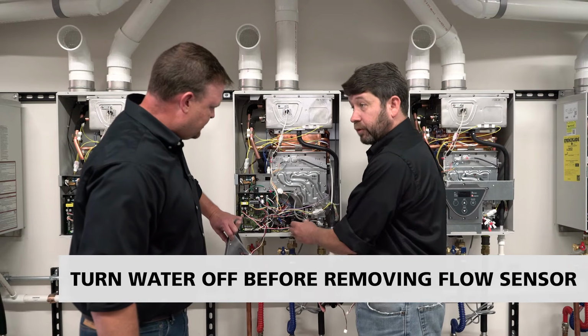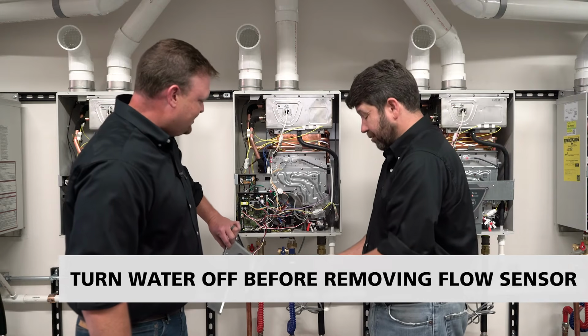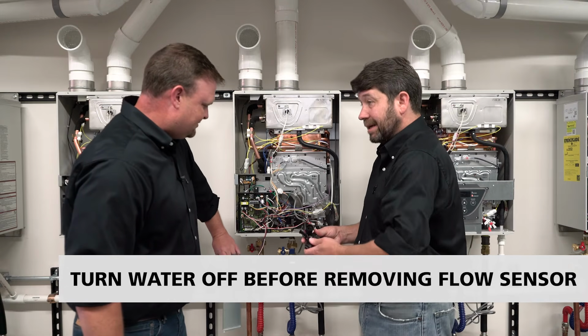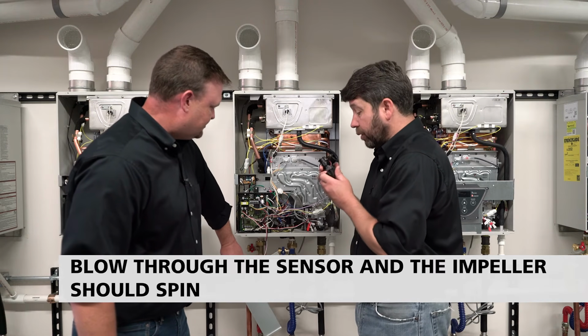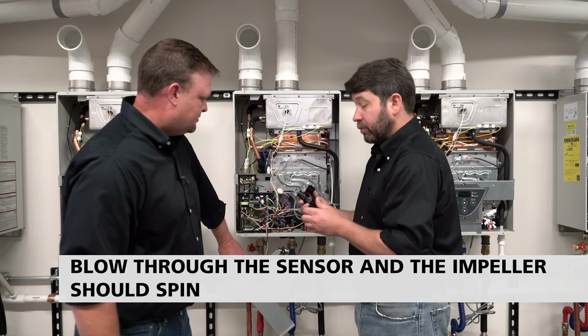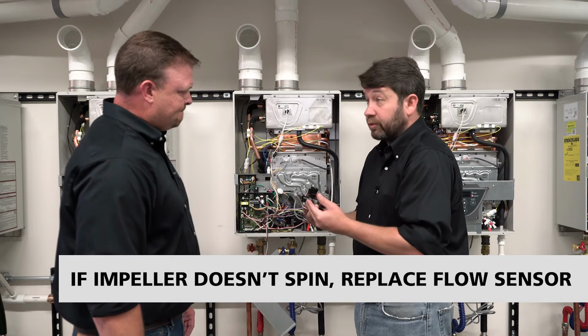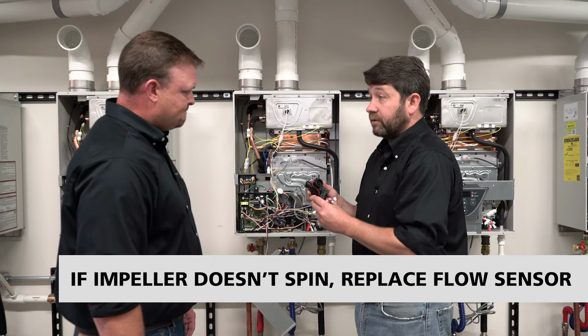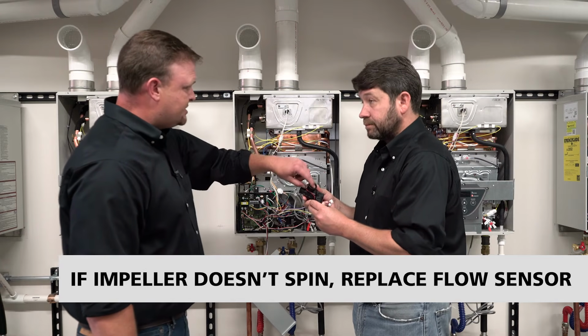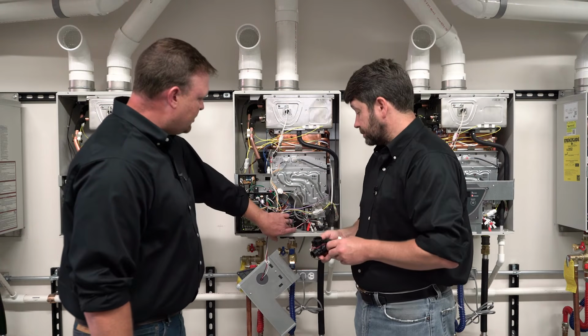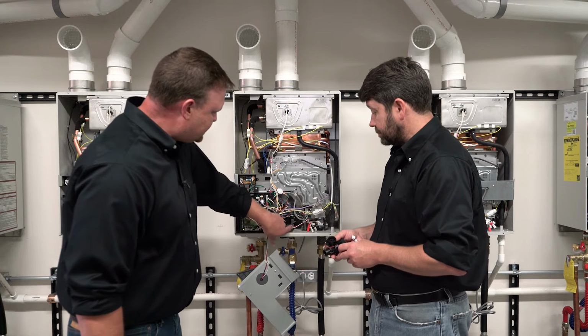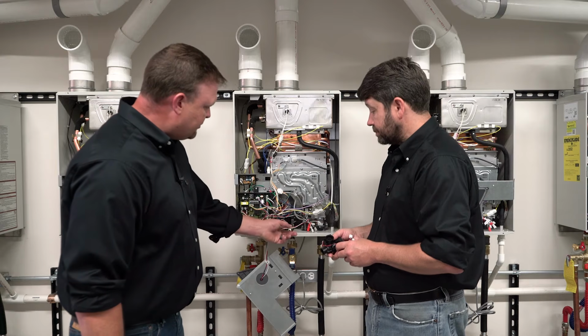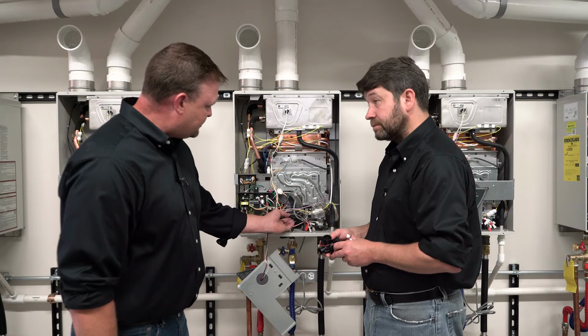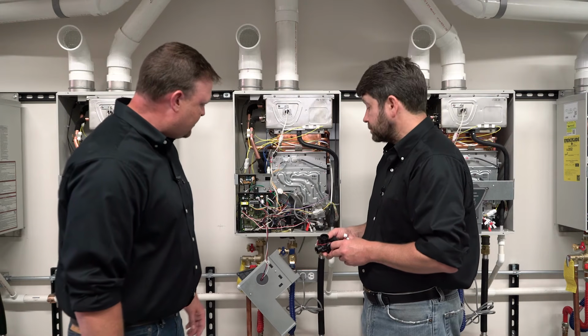Now we want to make sure that the water's off before we take these clamps off, so we don't have any water damage or spray any water. That would not be nice. But this is a pretty easy thing to check. We're just going to blow through it, and we should be able to see the impeller spin there. If we can't blow through it, or if the impeller doesn't spin, we'll have to replace this. So we would remove the two clamps. It's pretty simple. Once you remove the bottom clamp and the side clamp, just lift it up and over, and it should come out pretty quick.